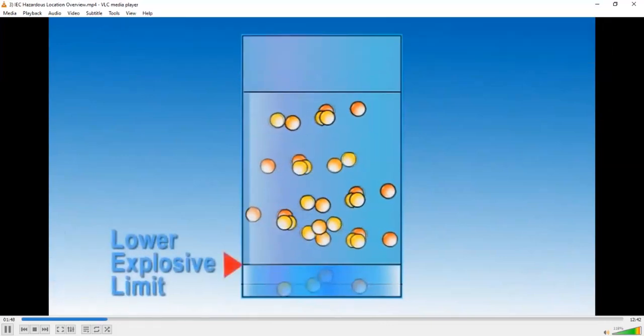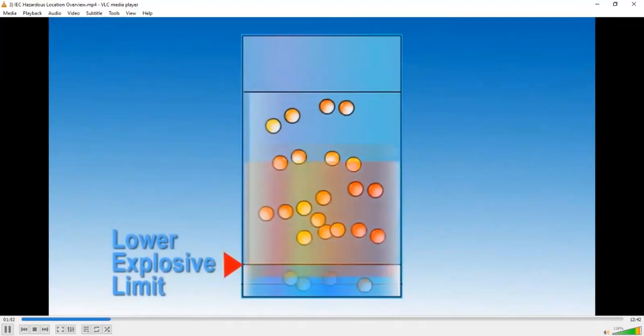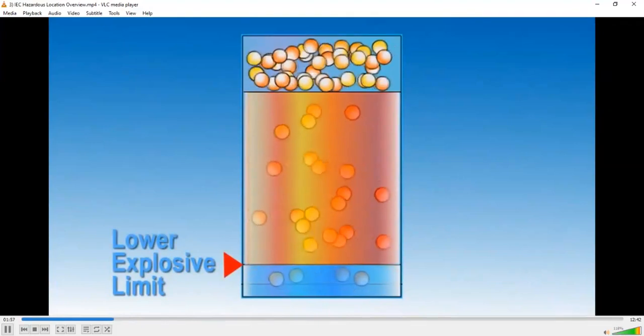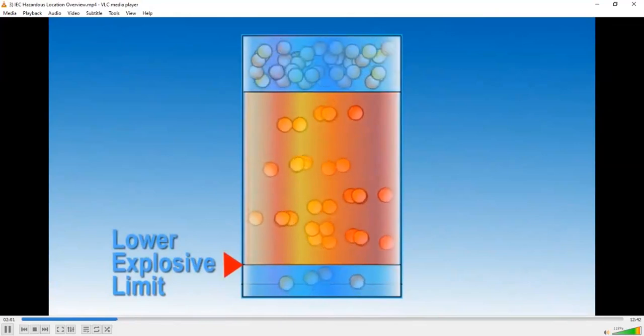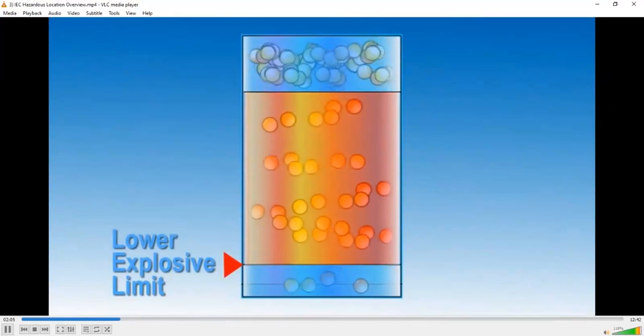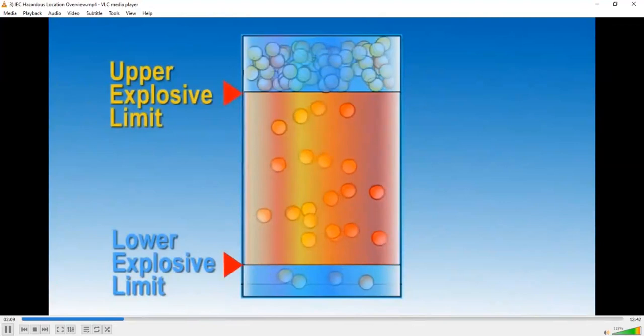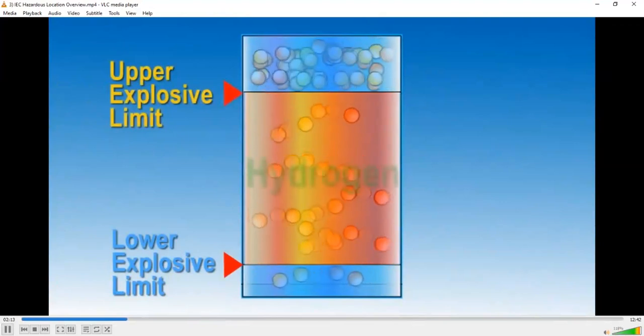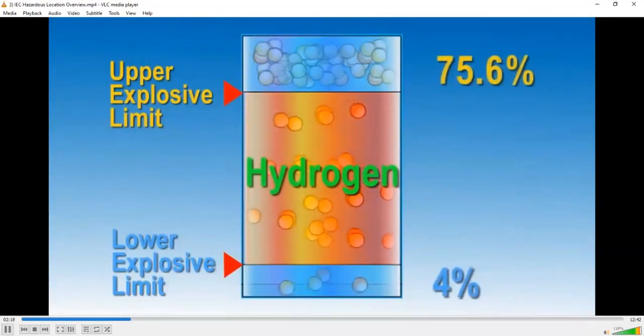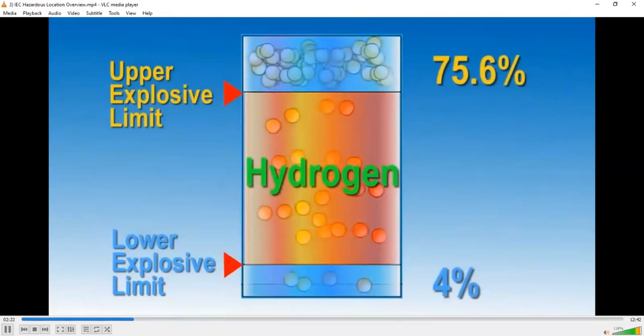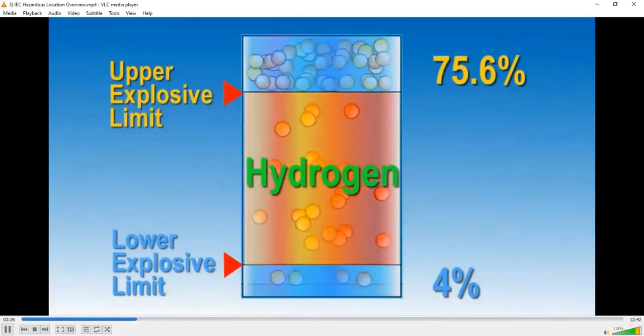Another key factor in a fire or explosion are the explosive limits. These are the maximum and minimum concentration needed of a given combustible material to support a fire or explosion. To form an explosive mixture, the hazardous gas must have sufficient concentration levels. The minimum concentration of combustible material in air is known as the lower explosive limit, or LEL. If the concentration is below the LEL, it will not be flammable or have enough flammable material present. The same condition would apply if the gas concentration is too rich, meaning it will not ignite because it will not have sufficient oxygen to sustain the fire or explosion. This is known as the upper explosive limit, or UEL. It should be noted that different gases will have different threshold limits. In this example, the LEL of hydrogen is 4%, and the UEL is 75.6%. Therefore, any mixture of hydrogen and air that falls between these limits will be a flammable mixture.